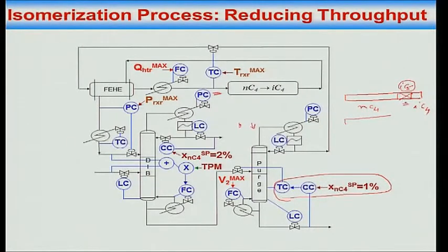Just like I decrease this, I am going to decrease this too. How do I decrease this? By cranking up this boil up, by increasing the ratio set point, boil up to feed ratio set point. As I am increasing this ratio set point, what will happen? Boil up increases. If boil up increases, the amount of IC4 that's leaking down decreases, right? And therefore, in the same way as before, I will be sucking in more fresh feed. Yes or no?